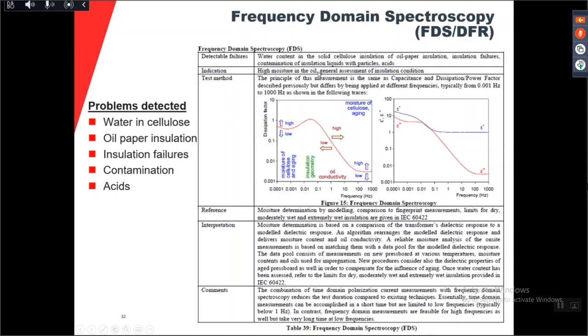So when you do a DGA and you get the moisture content in the oil, you say, oh, maybe I have also high moisture content in the paper, because those two are actually not the same. Moisture in oil and moisture in paper are not the same. Also, from the general assessment of the insulation condition, if you do a capacitance and dissipation factor or power factor test, you get a high power factor value, a high tan delta value. Why do I have a high tan delta value? You can do an FDS test and you can get a much better understanding of what's going on inside your transformer.